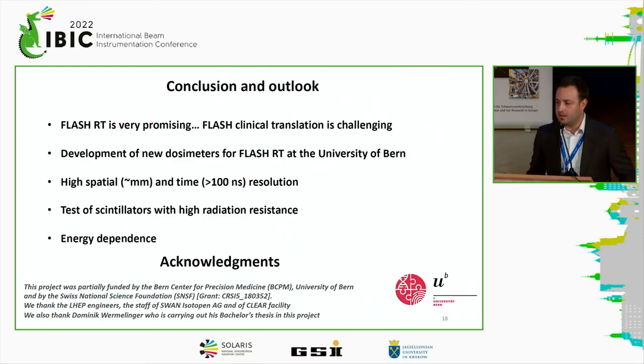Finally, to summarize what we did, we saw that flash radiotherapy is actually very promising. I would say it's a potential breakthrough in cancer therapy, but this potential is really important because, of course, this has to be verified. But the flash clinical translation is indeed challenging. So what we are doing at the University of Bern, we are developing a new dosimeter for flash radiotherapy. This dosimeter features millimeter spatial resolution and time resolution down to 100 nanoseconds.